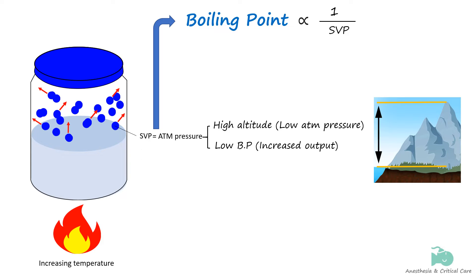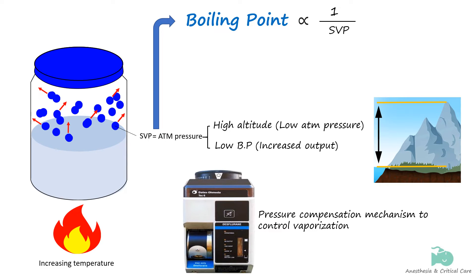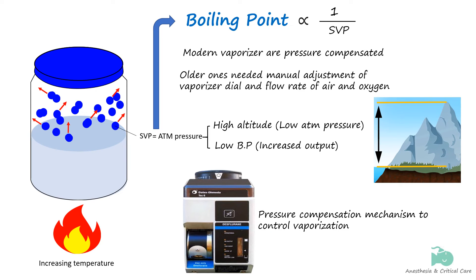You can check the table given in the earlier slide. For example, desflurane boils at 22.9 degrees Celsius at an ambient pressure of 760 mmHg, meaning it easily turns into vapor at room temperature, making it challenging to control its concentration during anesthesia. For this reason, desflurane vaporizers have mechanisms to compensate for changes in atmosphere. Modern vaporizers for most agents automatically adjust for altitude changes, ensuring safe dosing, while older vaporizers may require manual adjustments at higher elevations.